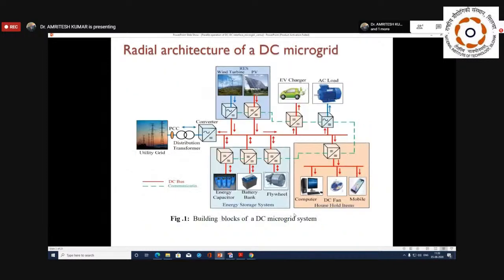If you see the architecture of a DC microgrid, it's simple. Shown here is the radial architecture of a DC microgrid. You can see the utility grid and a single radial line. On that, many sources are connected, including AC load and DC load, multiple loads on one single line. Through a converter, this is connected to the utility grid, so the converter acts as a link between the grid and your DC grid. If the utility grid fails, this whole system may act as an independent unit and has to sustain whatever load is there in the localized unit.